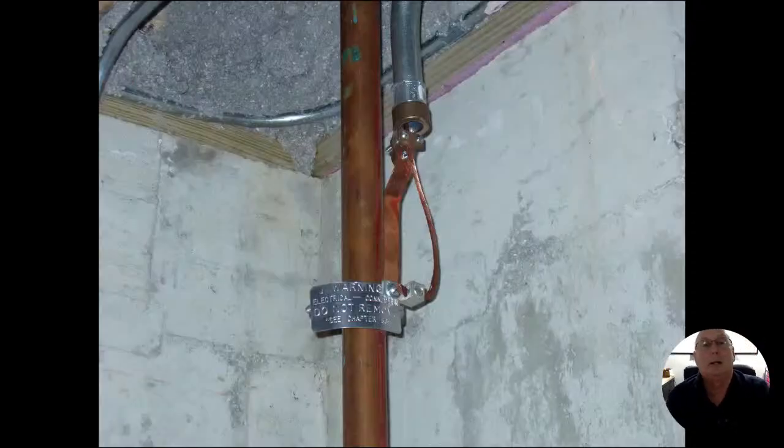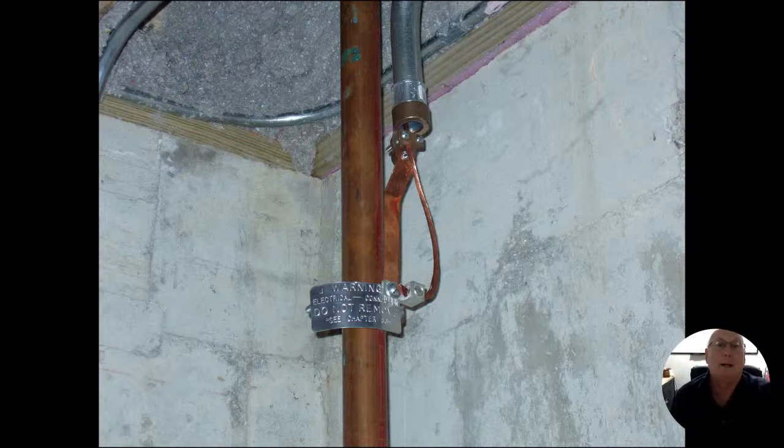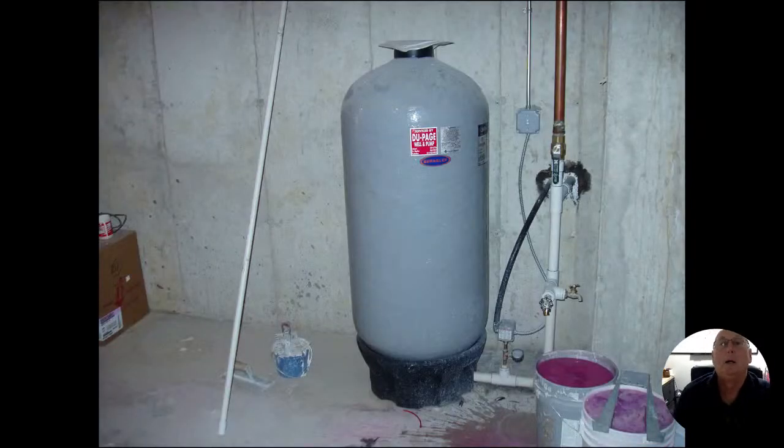So this is just another connection for our water pipes. This is that Chicago ground that I talked about. Comes out of the electrical panel, goes to the closest water meter. If we have a plastic water feed coming in here, this is not going to do us any good whatsoever. I would still try and get some sort of connection for these water pipes to still be part of the grounding system. So I would still get them connected to it, but we're not going to be connected to the earth. More or less we're bonding the plumbing system to the ground rods outside, to the ground system, so they all stay the same potential.